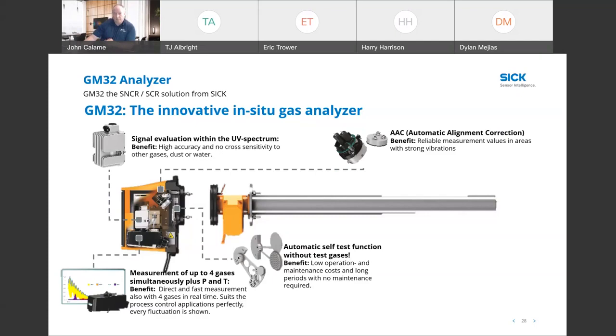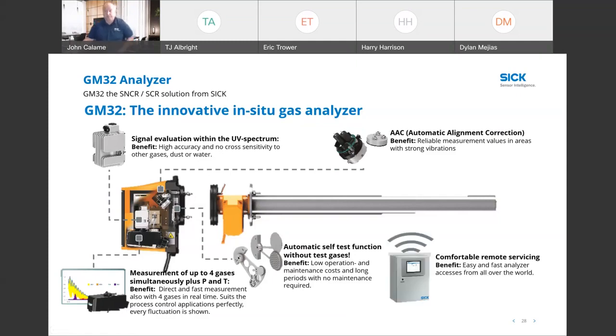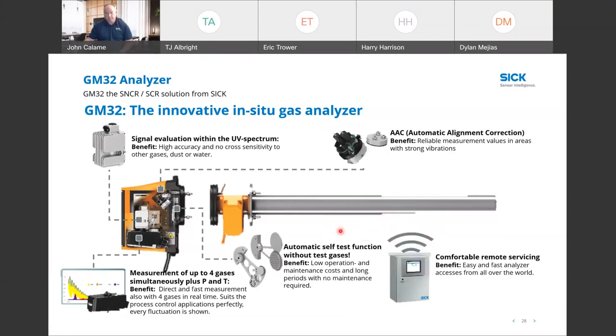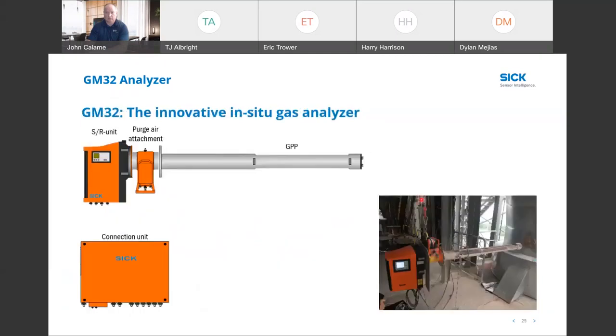No. So the good thing about this is the GM32 actually comes in 3 different configurations. So John mentioned that. I mean, you see the probe right here. So this is the purged air probe. If you don't need to put it on test gas every now and then, you can go with this one because it's going to be an open path purged air probe. There is a filtered probe. Usually it's going to be a ceramic filter, just because of very high temperature, the Teflon filter typically won't hold up. And as well it does have a cross-duct application. Usually the installation is a lot easier for a single-sided insertion, but it does have a cross-duct application as well. So that's going to be what John's showing you here, is the GPP.